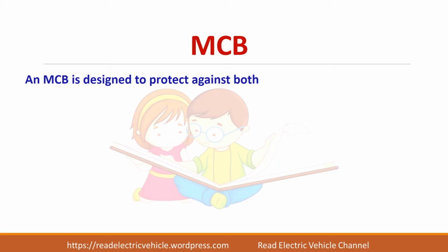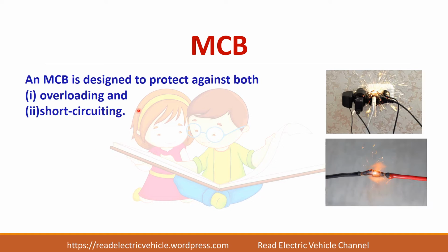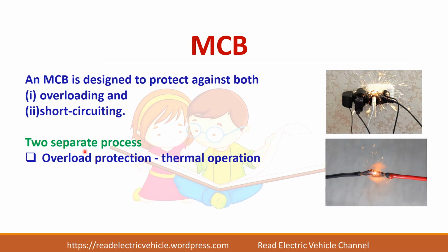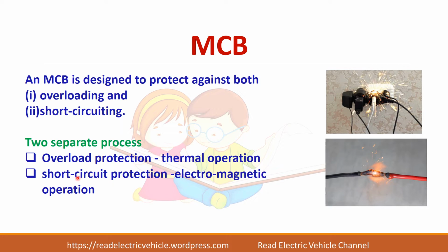An MCB is designed to protect against both overloading as well as short circuit. So these two are two different processes. Under overloading condition, the temperature increases and a bimetallic strip bends so that the MCB gets tripped. So thermal tripping is used for overload protection. For short circuit protection, a solenoid and a plunger is used. When a short circuit current flows, the solenoid gets activated and it moves the plunger. So due to that, MCB gets tripped.